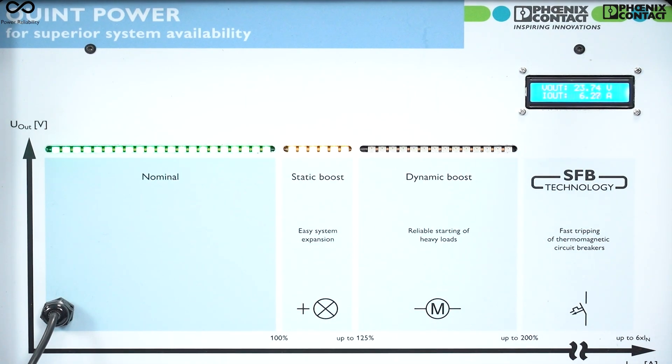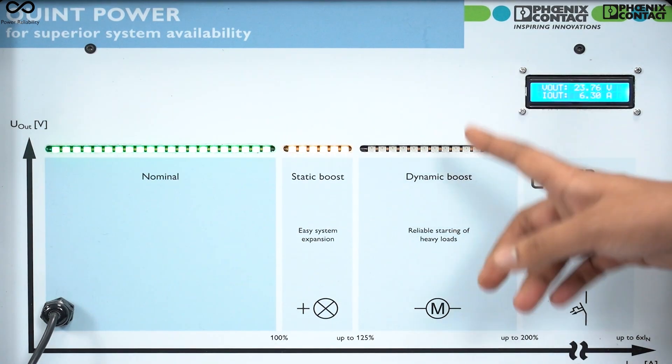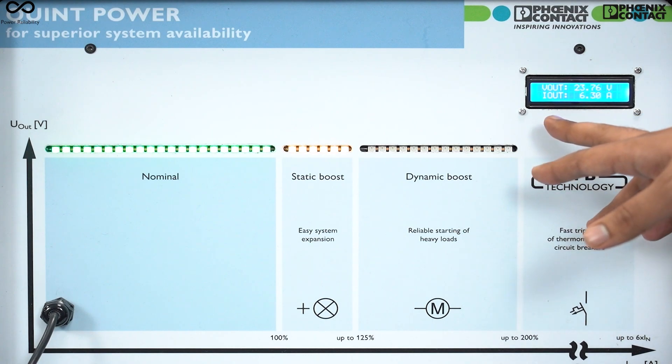Now if I make the power supply work in dynamic boost, you can see the power supply can give two times of the rated current only for five seconds. This is the value shown here. I'll show you again in static boost condition, you can see the output current of the power supply is more than 6.25, that means it is additional 25 percent of the current being withdrawn from the power supply.